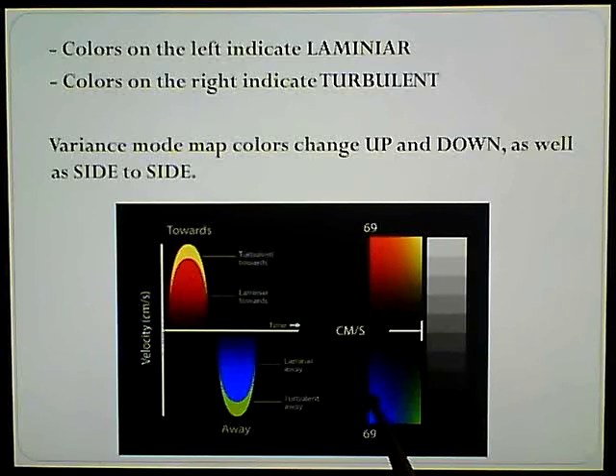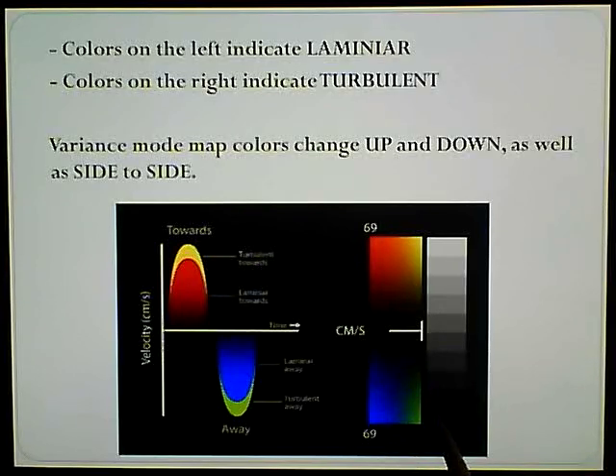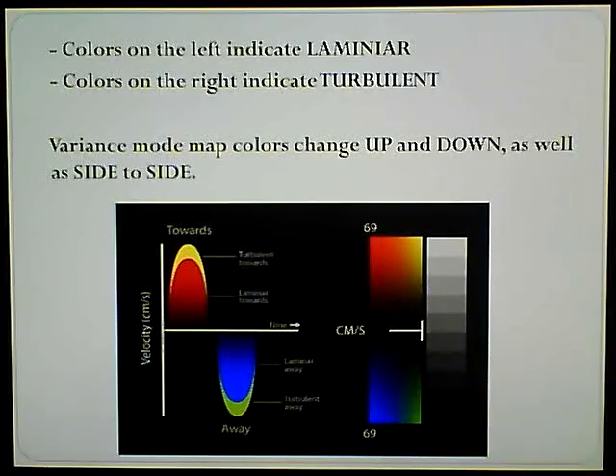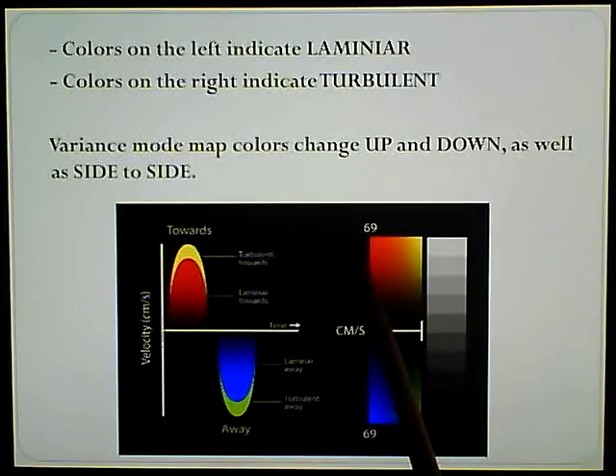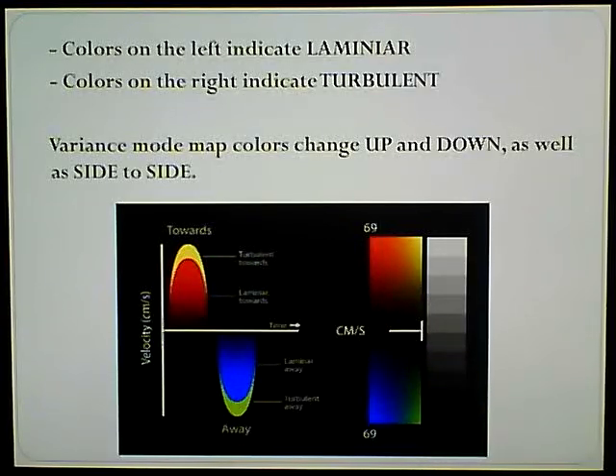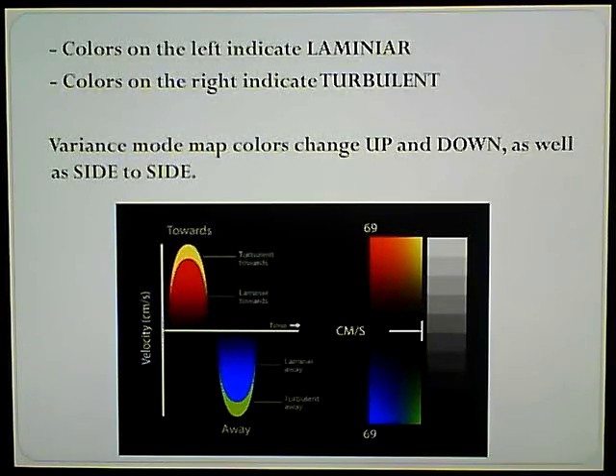From left to right - the colors on the left indicate laminar. See how smooth and even this red is? And the colors on the right are turbulent - it turns into kind of that greenish-yellow type color. Same thing down here: nice even blue, see how they change from left to right to that green - laminar to turbulent. You still have towards and away, but also that left and right laminar to turbulent. The variance mode map colors change up and down as well as side-to-side.